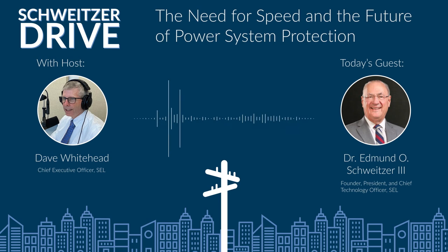Well, one thing we're discovering is you get a very good recording of effects inside the circuit breaker, such as restriking. So when a breaker restrikes, that's an undesirable phenomenon, and it oftentimes means you need to do something for the breaker. But it's also interesting that it relaunches a traveling wave, and frankly, we can use those traveling waves to refine where the fault is located if we wanted. There's other things we've been able to see.